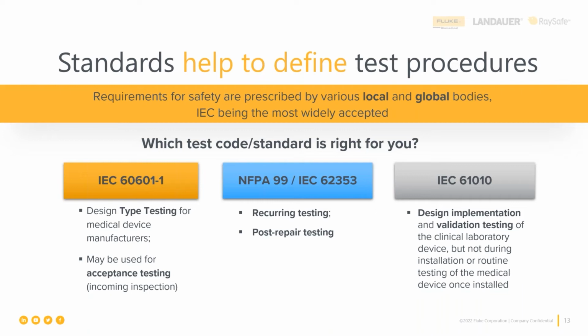Number one, when we talk about electrical safety and we're talking about the IEC 60601-1, it is important to use that whole name. The reason for this is that the IEC International Minimum Performance and Safety Standards for all categories of medical devices fall under an umbrella called IEC 60601. So if you shortcut and say IEC 60601 and you're talking to me, I'm thinking you're talking about the big umbrella. If you're really talking about the electrical safety, then I need you to clarify and say IEC 60601-1. That tells me immediately you're talking about electrical safety, not everything under the umbrella. Okay, so don't get lazy here. Use the full term, the full name of the thing.